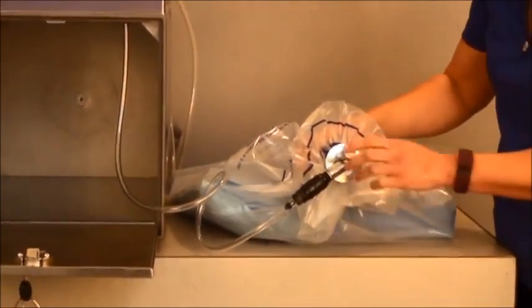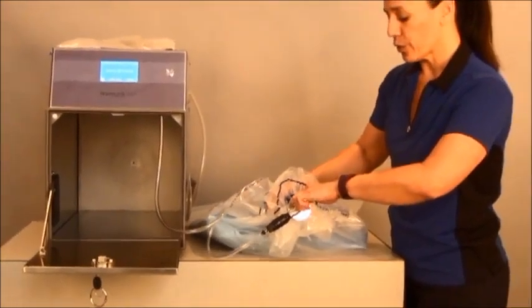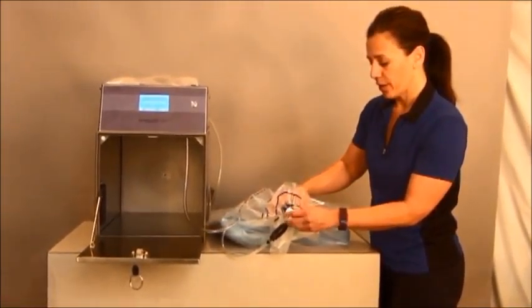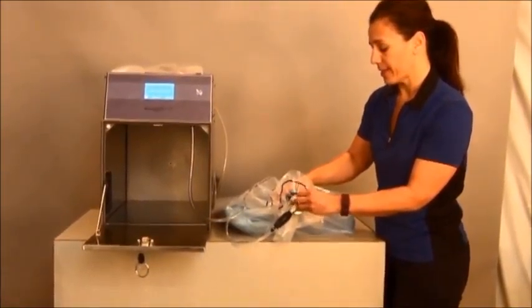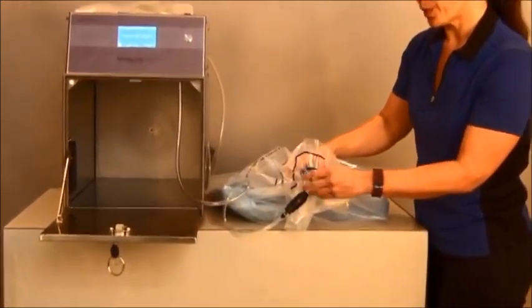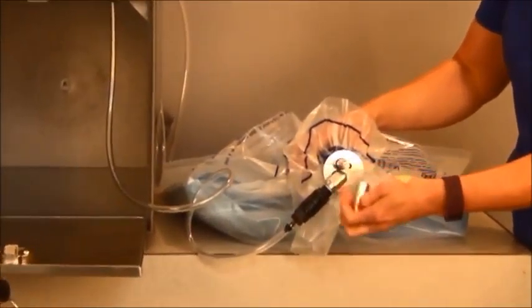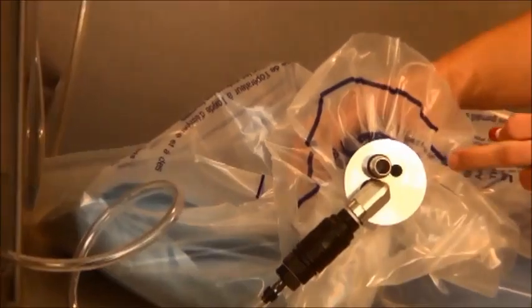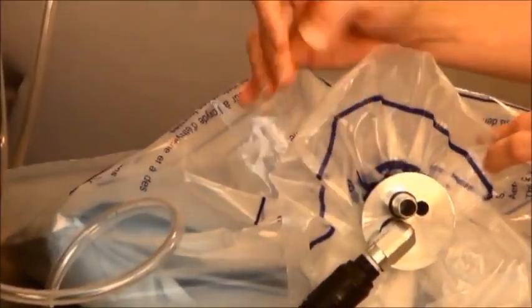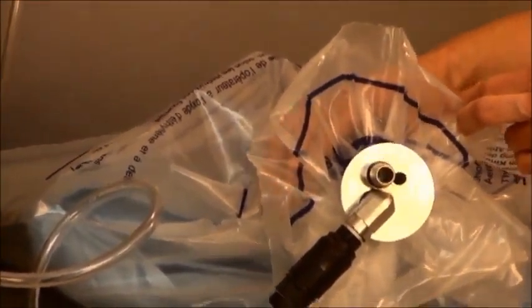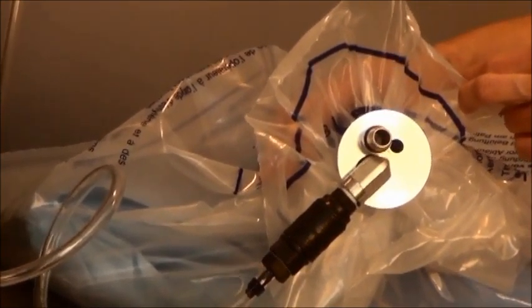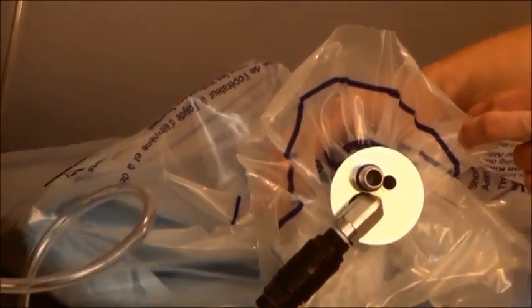At this point in time, you can unscrew the top portion, which is your process challenge device. This is where you're going to put your biological indicator. We have tested and validated that this location is the most difficult place for gas to reach and for sterilization to be achieved.